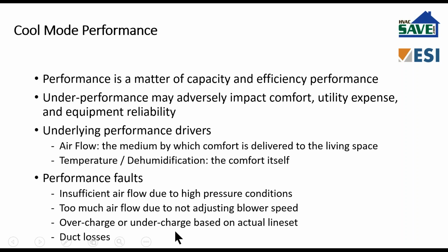The overcharge and undercharge faults, okay? So again, the factories ship out a default amount of refrigerant. That's based upon an assumed line set, which rarely is the case in the field, okay? So it's possible that you've got an overcharge or an undercharge. And then duct losses, duct airflow losses, duct temperature losses, particularly in the supply run.